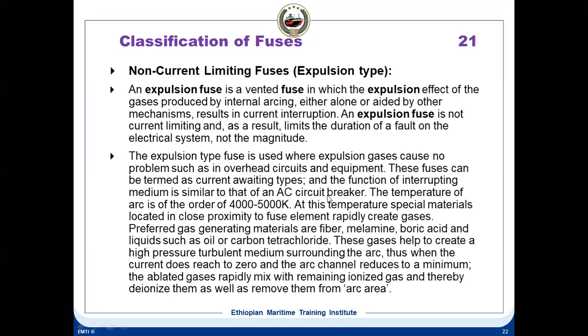When the temperature of the arc is of the order of 4000 to 5000 K, at this temperature, special materials located in close proximity to the fuse will rapidly create gases. These gas generating materials are like fiber, melamine, boric acid. There are different types of materials. And this gas will create a high pressure turbulent medium around the arc. And when the current does reach zero, the arc channel reduces to the minimum. This is the way it is extinguishing the arc, because of the gas which is inside. So this is called expulsion type. That is known as expulsion type.